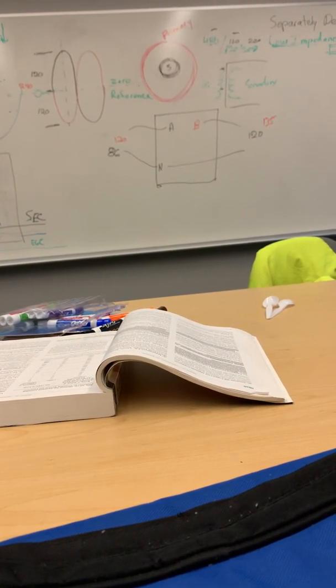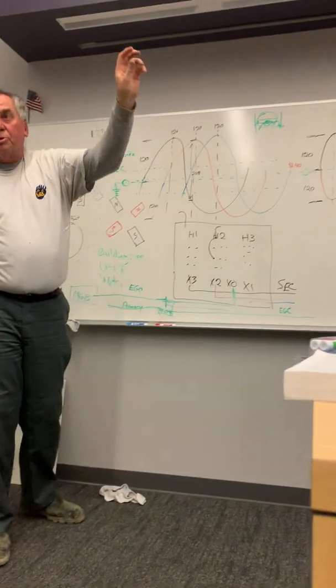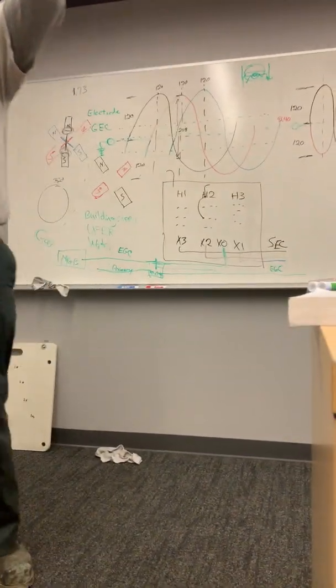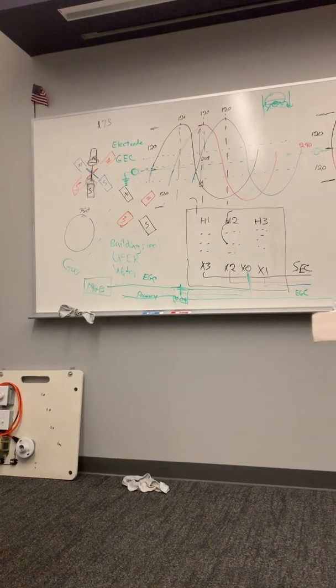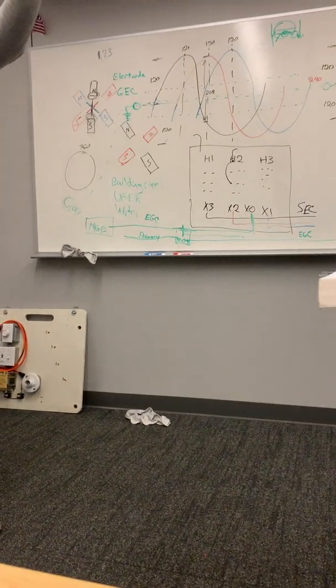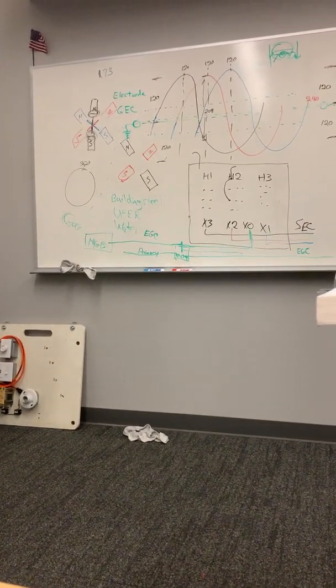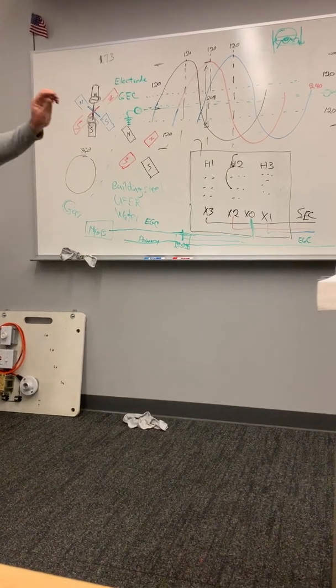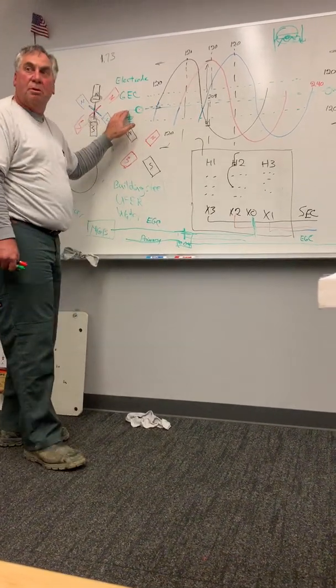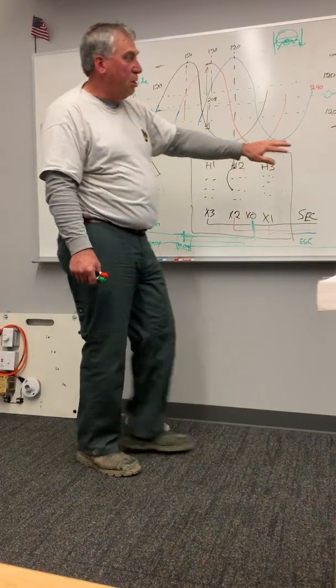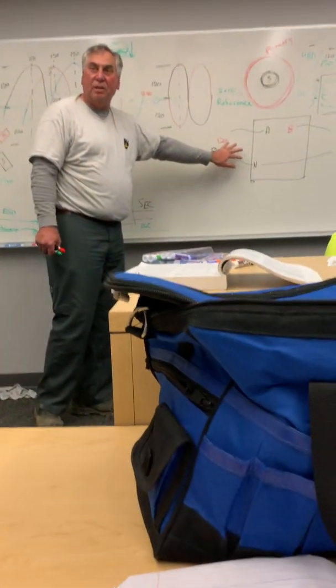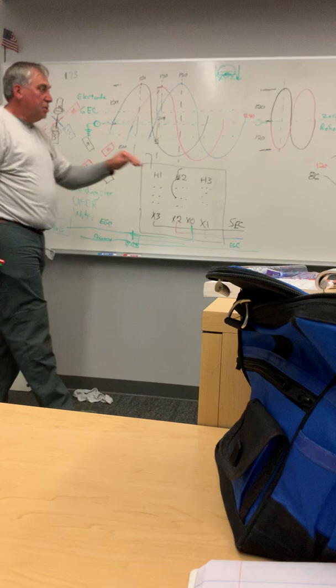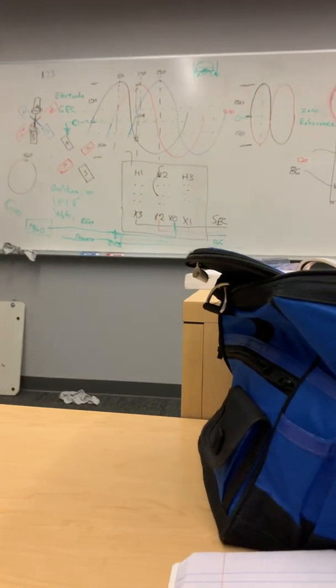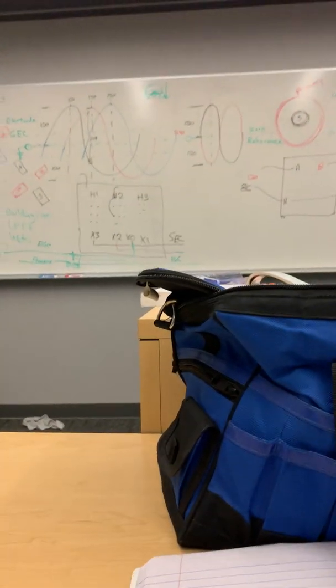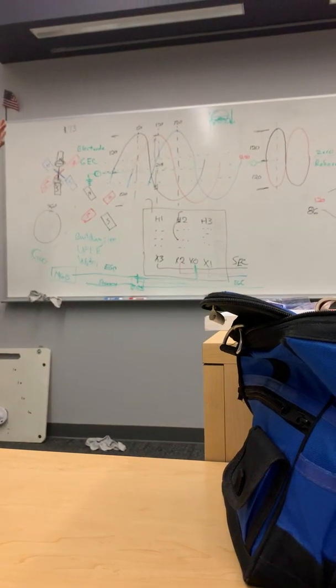We live in the mountains, and the triplex coming from the transformer was going through a tree. The two hots made it through fine, but the neutral was broken in the tree. So now we've got no zero reference, and this thing is all over the map with crazy voltages. So I said, hey, you've got to call PG&E and have them come out. Sure enough, they found the break in the wire and put it back together.